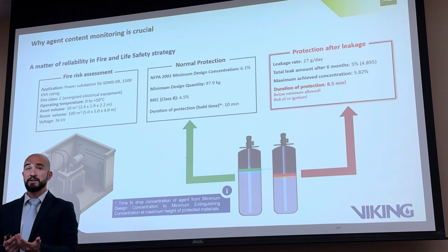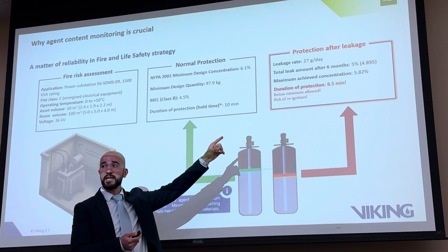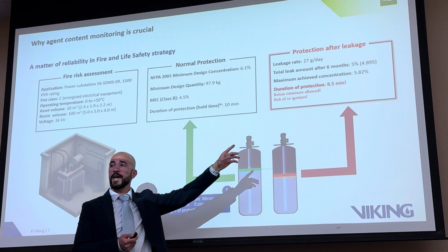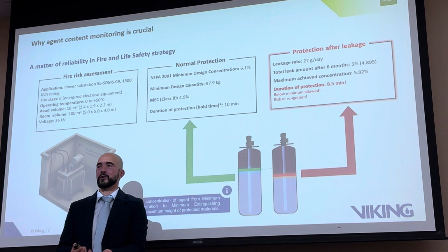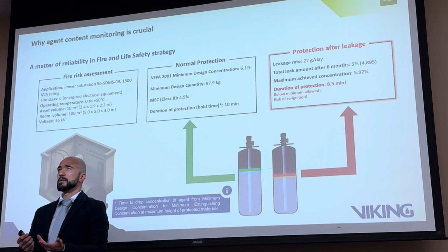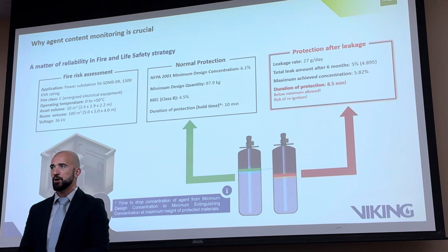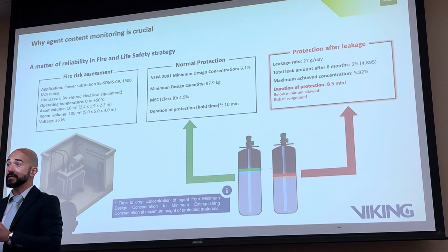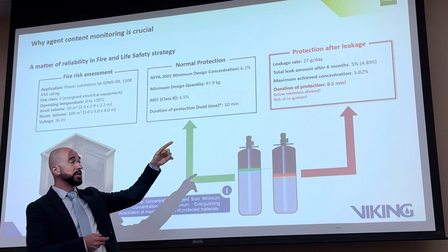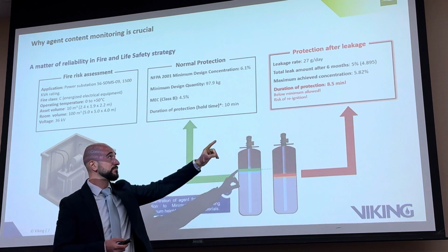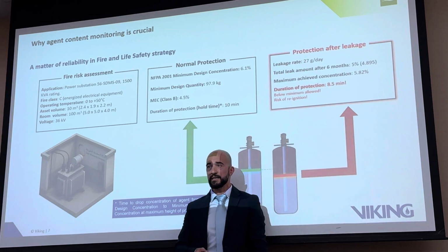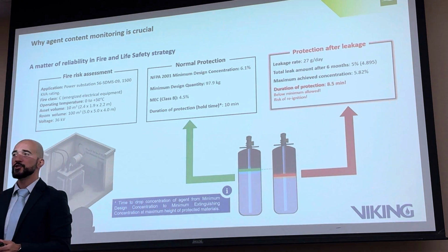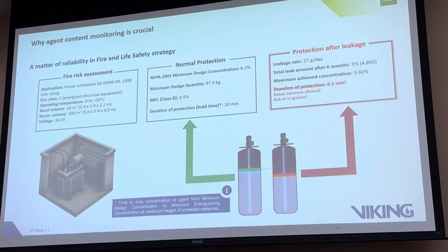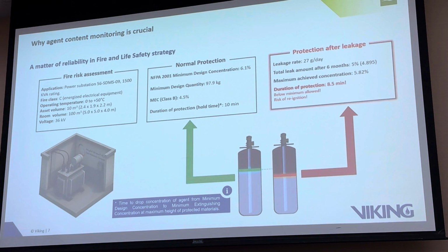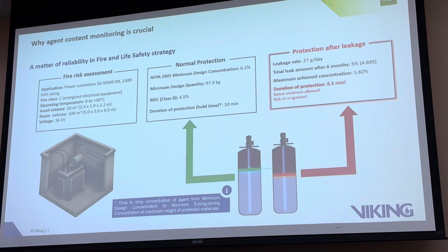But on top of that, there's safety. Instead of a 10 minute hold time, that will reduce to 8.5. You would say, Adrian, it's 1.5 minutes, if the fire brigade has to come in, that doesn't make much difference. It does, why? Because number one, it's below the minimum allowed, no compliance, but second, because of the risk of reignition. These 10 minutes are not designed to give time for the fire brigade to arrive, they're scientifically proven to be enough to prevent reignition. So that's the big risk of such a small leakage.